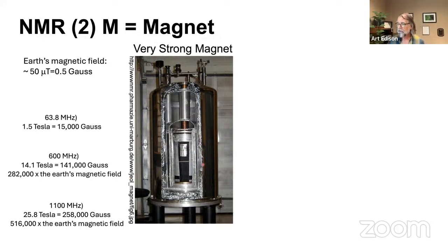So this is what a magnet looks like. This one has been sacrificed just as a demo so that we could see this neat stuff. On the inside are the coils that make up the magnet, and surrounding the coils is a thermos that holds liquid helium, so they can be superconducting, and on the outside another thermos that holds liquid nitrogen that keeps the liquid helium cold.